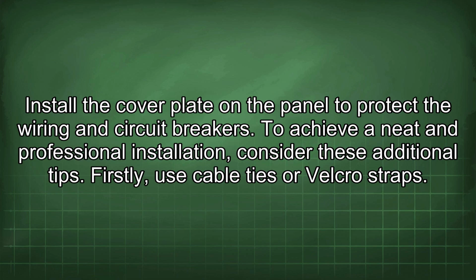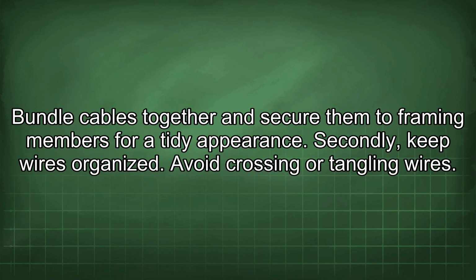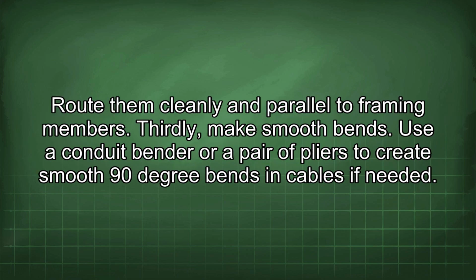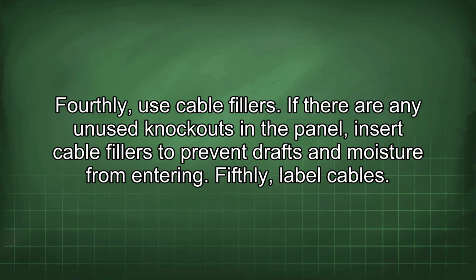To achieve a neat and professional installation, consider these additional tips. Firstly, use cable ties or Velcro straps. Bundle cables together and secure them to framing members for a tidy appearance. Secondly, keep wires organized. Avoid crossing or tangling wires. Route them cleanly and parallel to framing members. Thirdly, make smooth bends. Use a conduit bender or a pair of pliers to create smooth 90-degree bends in cables if needed. Fourthly, use cable fillers. If there are any unused knockouts in the panel, insert cable fillers to prevent drafts and moisture from entering.